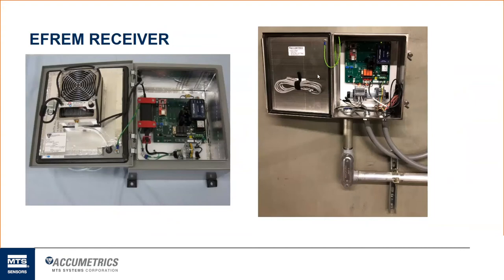To the right, just another example of a non-cooled version and what it may look like installed at a utility. This customer chose to mount this directly to the concrete bulkhead right below the exciter doghouse. They supplied the conduit that ran our coaxial cable up about 80 feet to the exciter doghouse, and all the outputs from our system run in other conduits off to the control room. So pretty standard stuff on how we would see our system installed at a power facility.